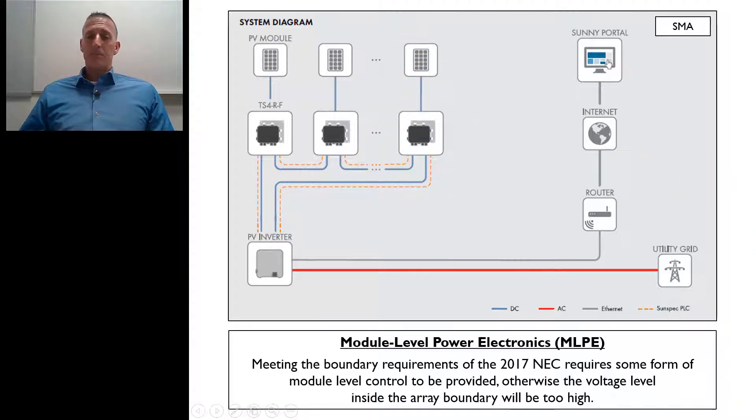So just basically the point of talking about this and showing this information on this slide is to let you know, to meet the rapid shutdown requirements of the 2017 NEC, we're now forced to use some sort of module level control in order to meet those requirements. String systems, the traditional ones that we've been used to, just won't meet this anymore.